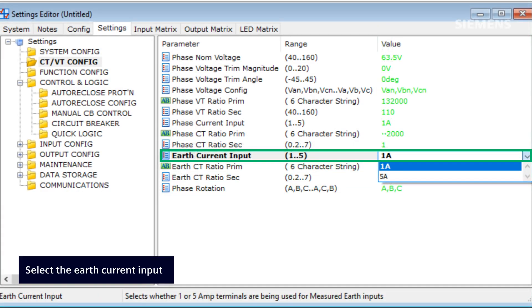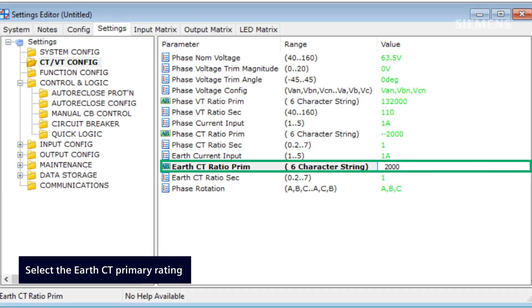The earth current input setting enables the user to select whether 1A or 5A terminals are used for earth CT inputs. The earth CT ratio primary setting enables the user to specify the primary rating of the earth CT, which is utilized to calculate the ratio for adjusting the primary earth current measurement in the instrument.